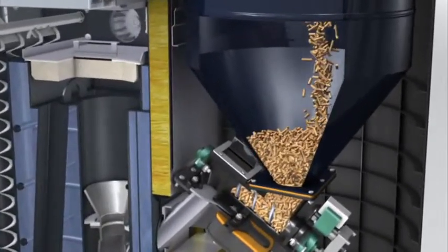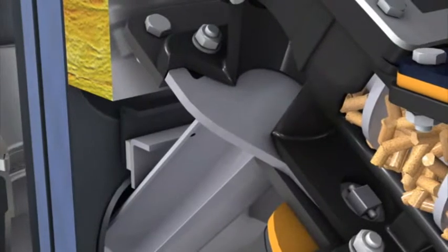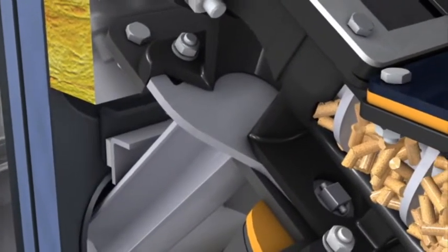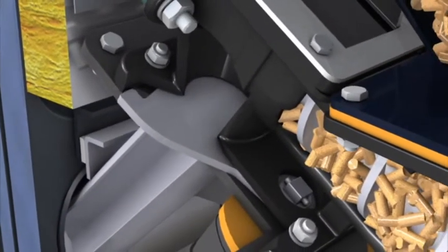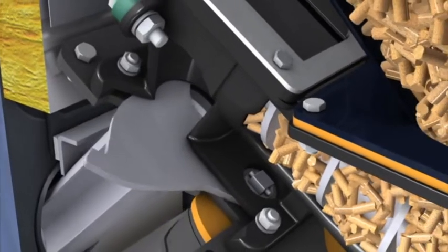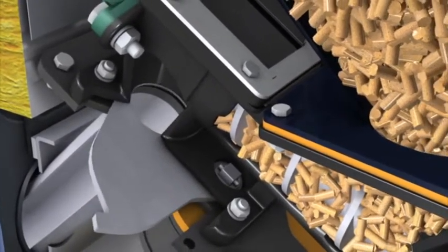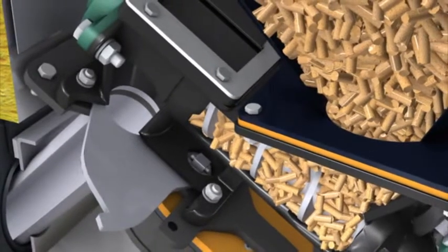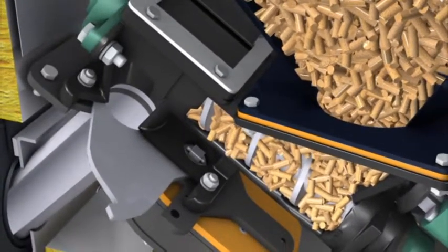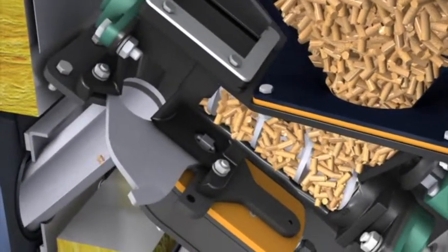A system self-test with automatic fault diagnosis is carried out each time the unit is started, thereby ensuring safe and reliable operation. The drop tube in conjunction with the safety-tested slide valve of the combustion chamber and the slide valve of the storage tank creates a double-lock system with a unique safety concept.